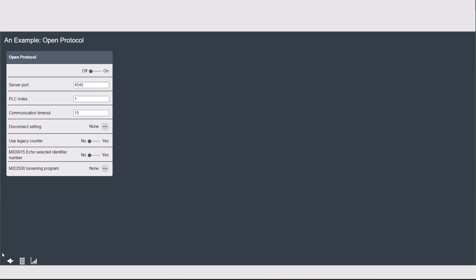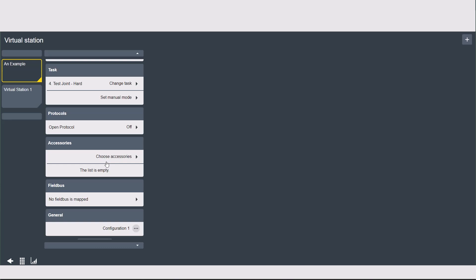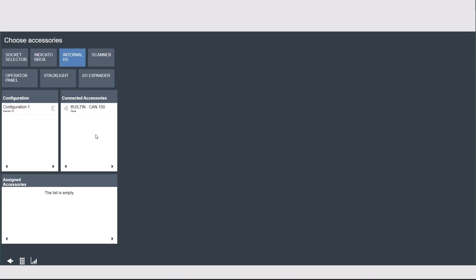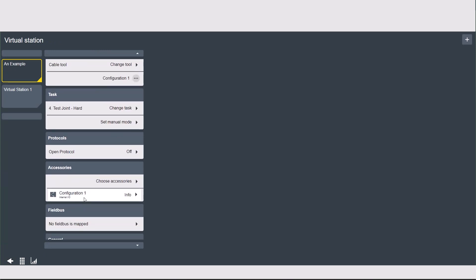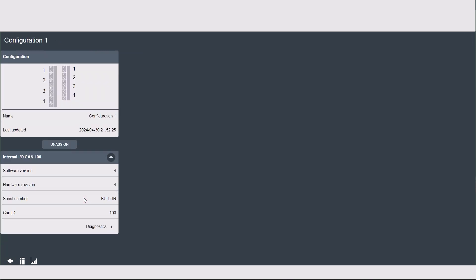Going back to the virtual station tab, next we have the accessories. Since we can have multiple tools and accessories paired to the same controller, we have to assign the accessories to the virtual station we want to use them with. Here you can see we are going to pair the configuration and the connected accessory together by selecting one of each puzzle piece. This is going to assign the accessory to the virtual station. Once assigned, the accessory is going to be grayed out with the virtual station name it is paired to so you will know it's unavailable for other stations. You can use the garbage can icon to unassign the accessory, and once connected you can click into this tab for more information and diagnostics. You can actually force signals if you have an IO assigned for testing.